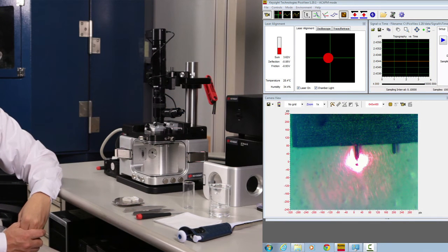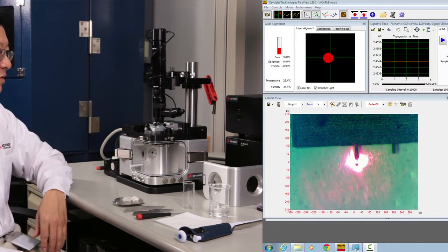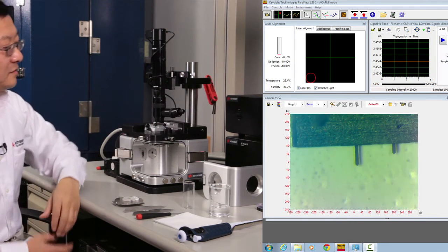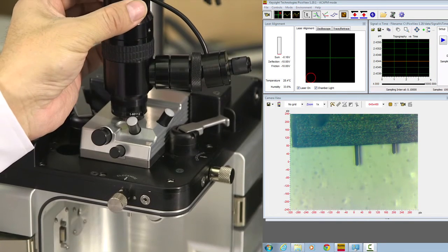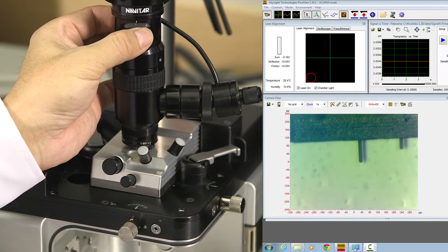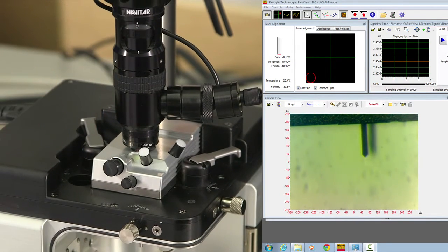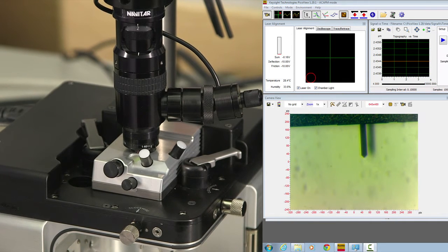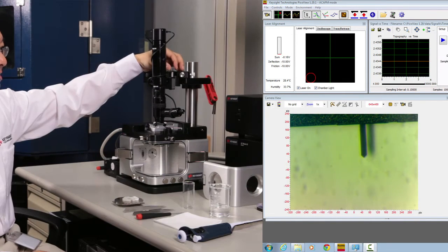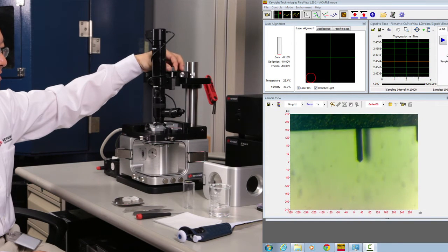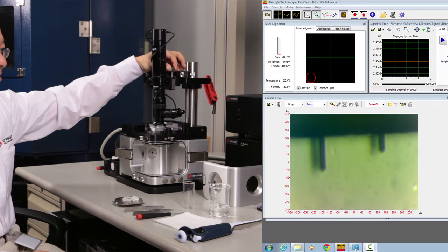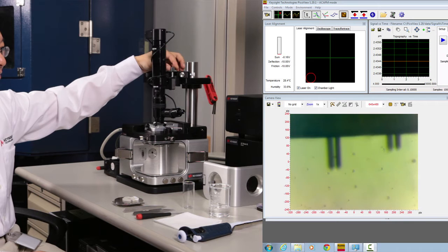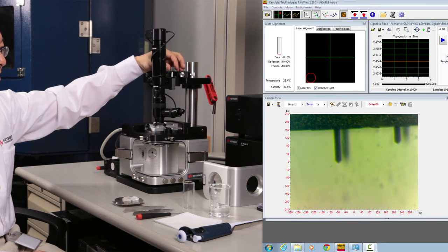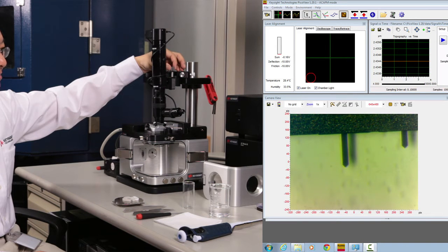You can also do this rough approach with the help of the optical microscope. Here's how to do that. First of all, turn off your laser, and then zoom in your optical microscope. Now take a look at the computer screen of your optical view. When it's zoomed in, you will find that there are two images of the cantilever. Move your focus up and down, and you will notice that the two images are at different heights. The first image of the cantilever on top is the image of the cantilever itself. The second one is the mirror image of the cantilever that's reflected from the sample.